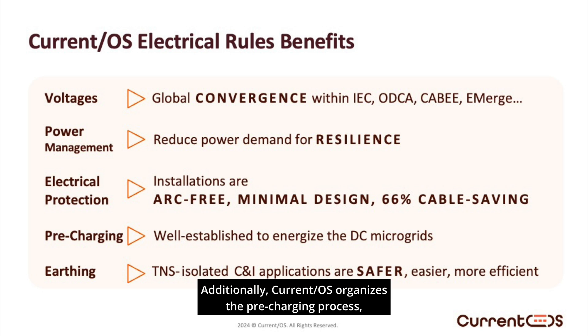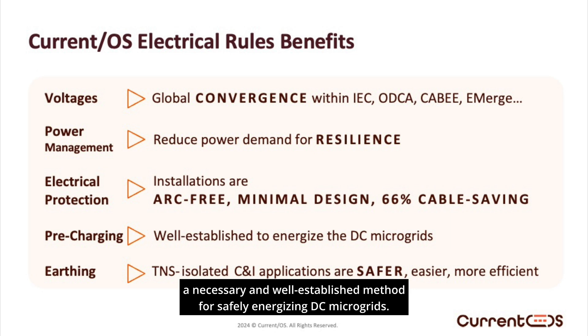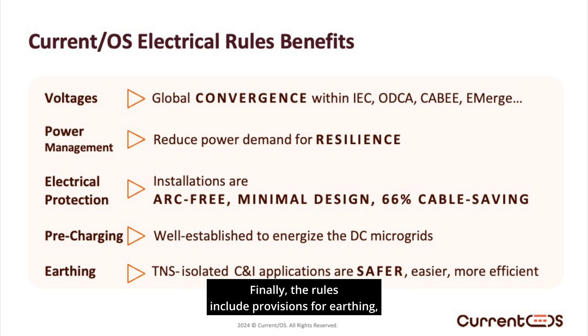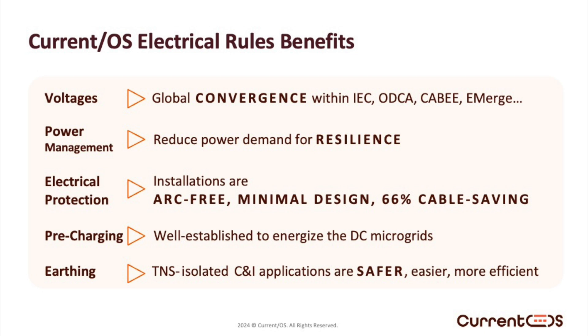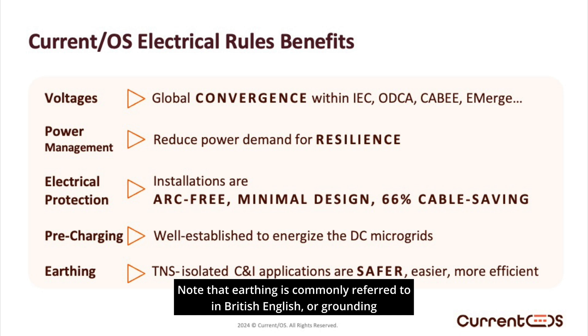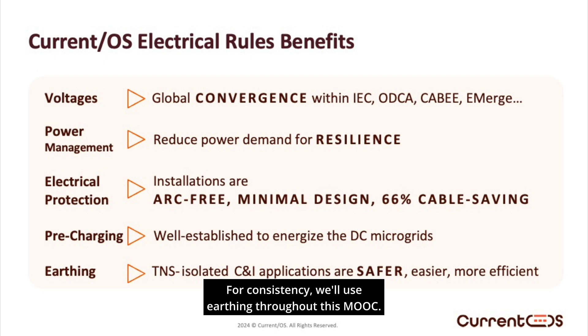Additionally, Current OS organizes the pre-charging process, a necessary and well-established method for safely energizing DC microgrids. Finally, the rules include provisions for earthing, recommending the TNS system alongside isolation between AC and DC installations. This approach is specifically tailored to the requirements of commercial buildings and installations. Note that earthing is commonly referred to in British English, or grounding in American English. For consistency, we'll use earthing throughout this MOOC.